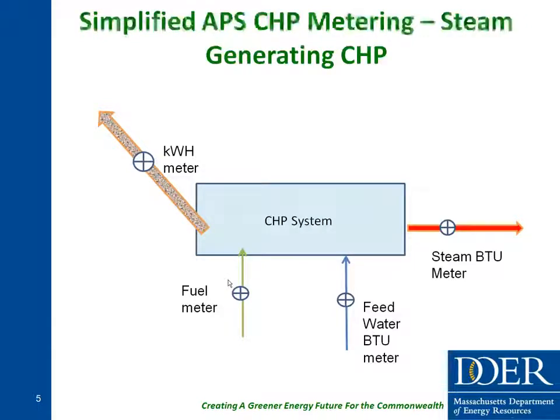A very simplified diagram of a typical CHP plant which is generating steam and requires steam energy metering. So I think the only important thing to see there, or maybe counterintuitive, is that you actually typically need 2 meters in order to get your net steam energy. You need a steam output meter and you need a feed water BTU meter so that you can actually come up with the net energy supplied. Next slide, please.